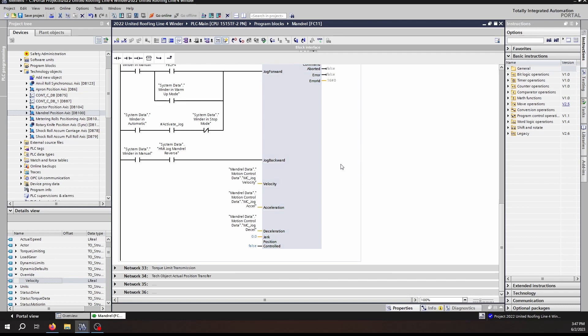Moving down the block, we see that we have a velocity, an acceleration, deceleration, and jerk, just as we've seen with a lot of our other motion control blocks. And once again we see that we have the position controlled input as we did in the MC Move Velocity. These inputs operate as you would expect. The velocity is in engineering units: degrees per second, millimeters, inches, feet per second, however you have your technology objects set up. Same with acceleration, deceleration, and jerk.